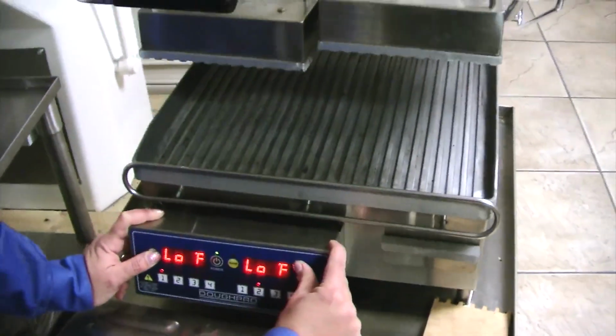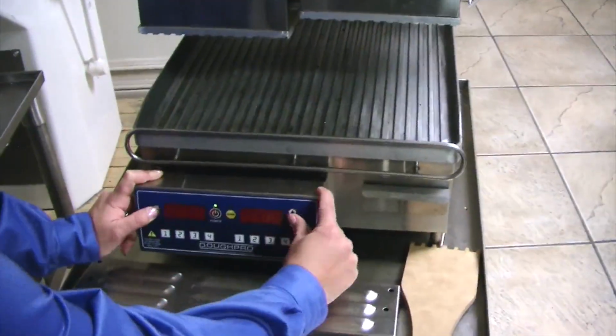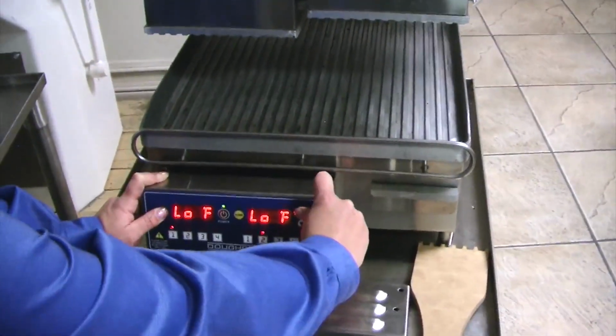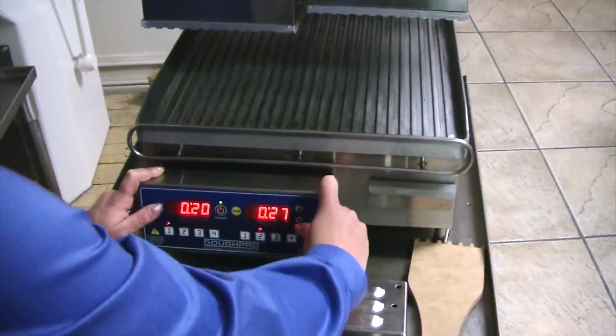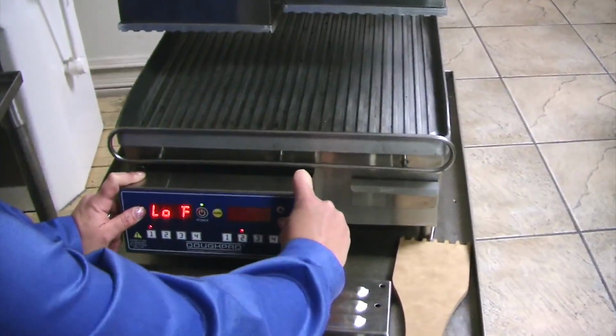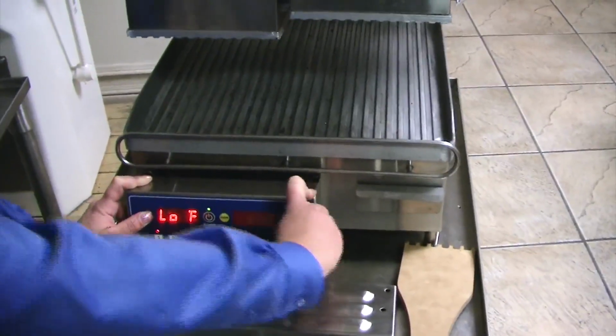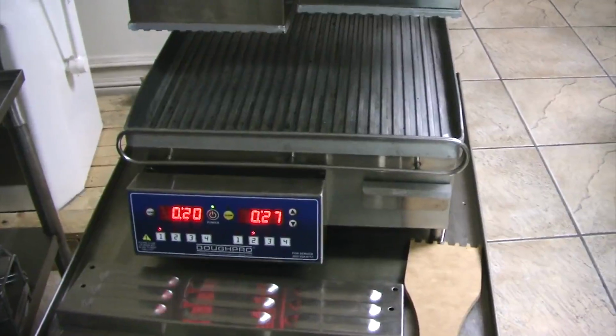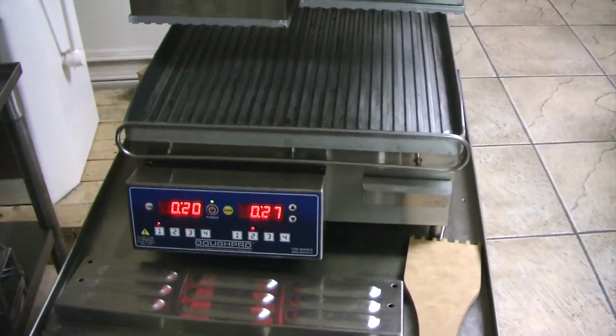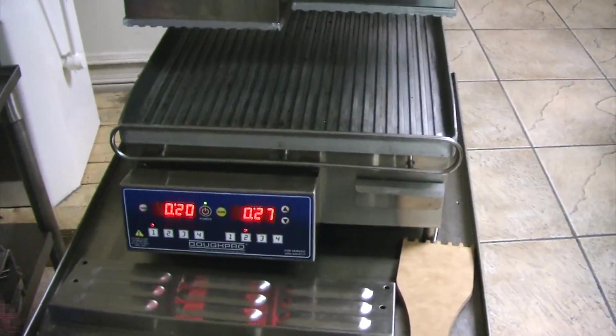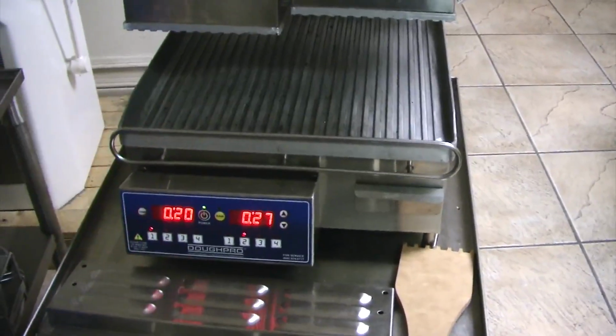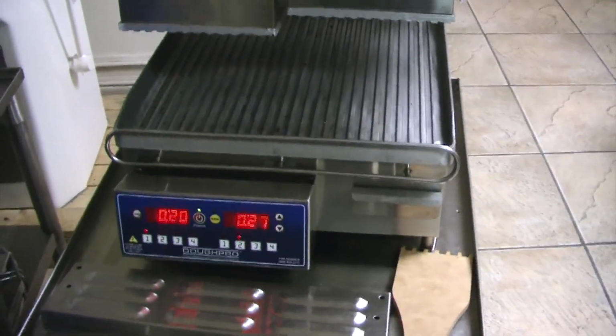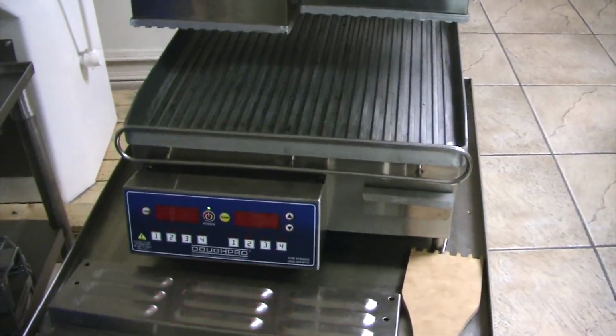So the left, and then this screen right here, the left, and then the right, zone 2, zone 3, down, zone 1. If it's giving you a probe reading on zone 1, then you need to check zone 1 in the back for your sensor to make sure that it's not broken. If it reads PROB, it means probe, not problem. If it gives you a relay, same thing. You want to go in the back and check for your relays. Make sure that they're not out.